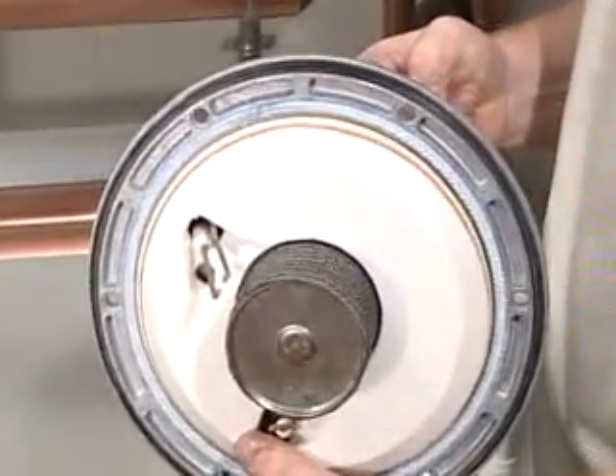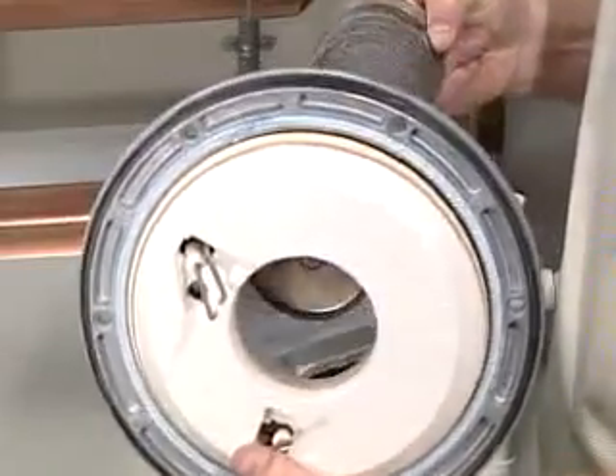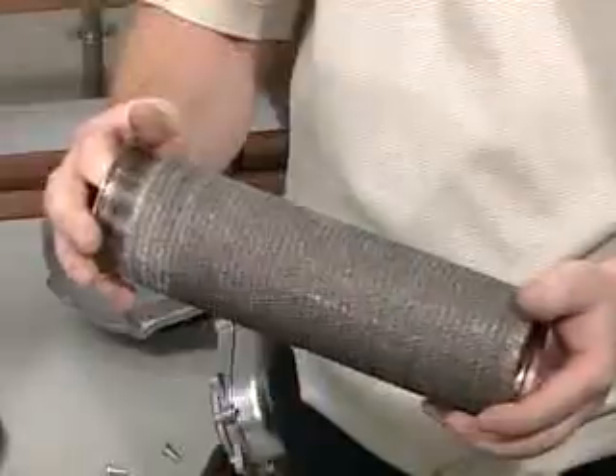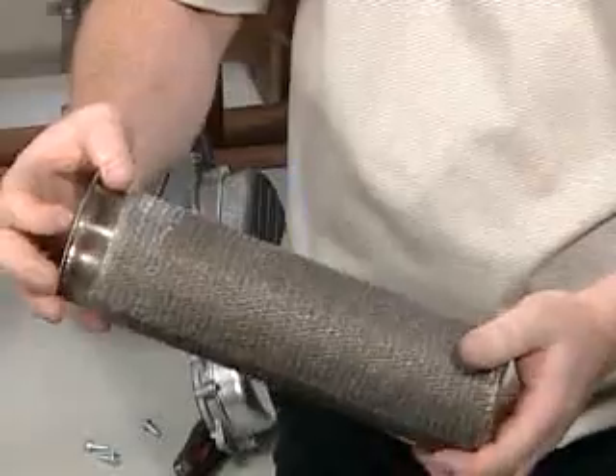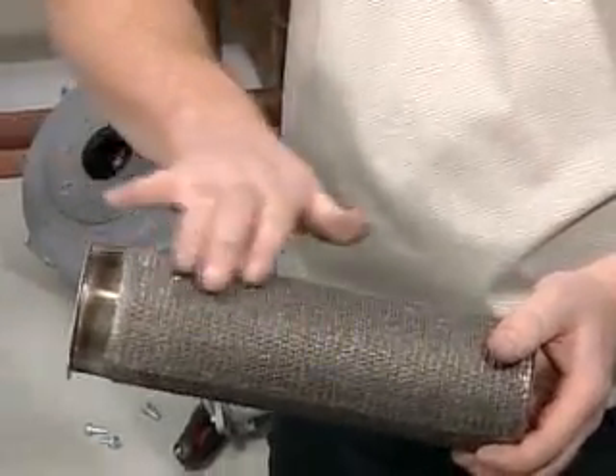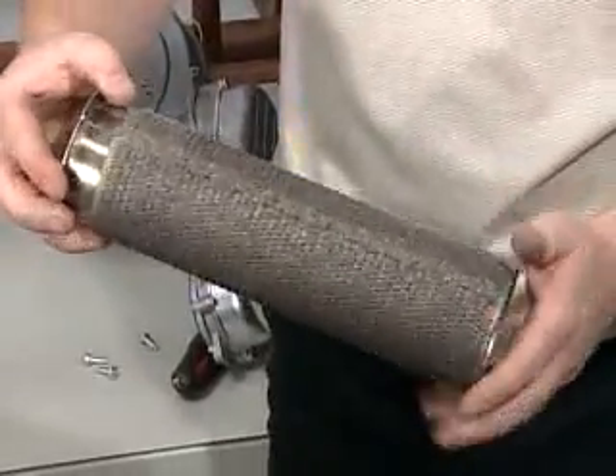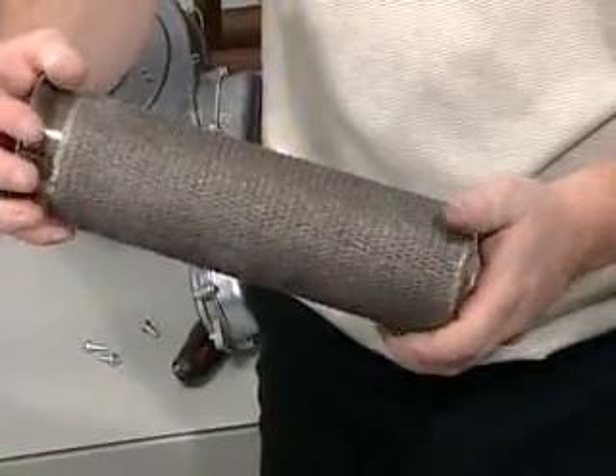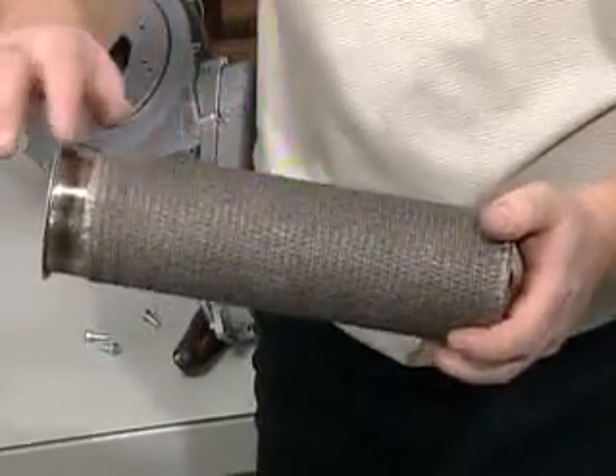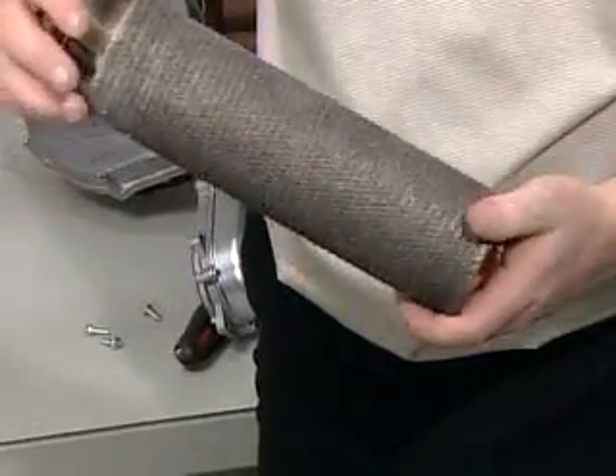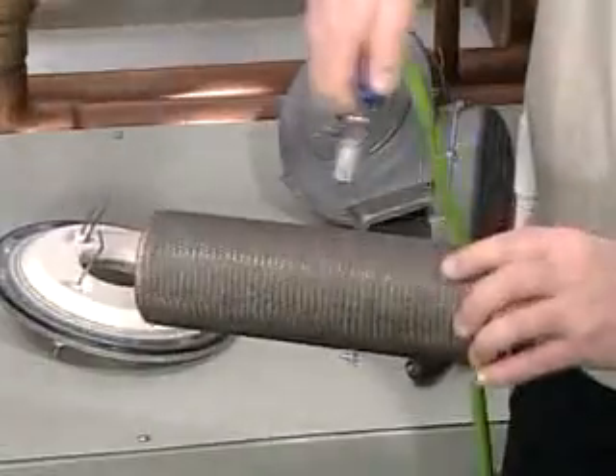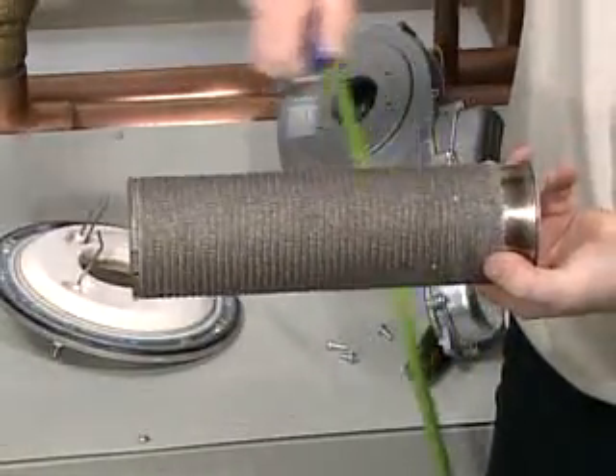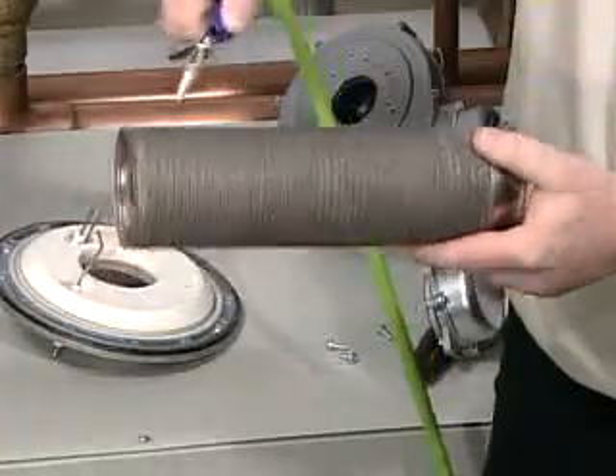Use caution when removing the burner to prevent damage to the refractory mounted on the inside of the heat exchanger door. Inspect the burner for any physical damage to the surface of the burner. If the burner surface is damaged, the burner must be replaced. If no damage is observed, clean the burner by using compressed air to blow through the surface of the burner.